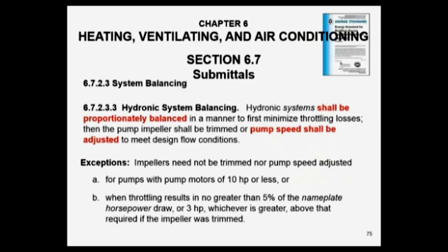All this means is if you did a true proportioning balance, then the valve would be wide open. It wouldn't be throttled. If we trimmed the impeller, we could reduce the horsepower. If you didn't want to trim the pump impeller, we could put a variable speed drive on it and slow it down, and we'll reduce the horsepower.